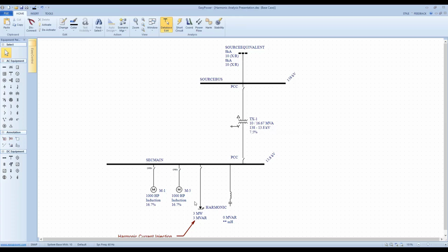If you are adding load, the purpose of the program is to take existing measurements at the point of common coupling and then add that additional load into your model with the measurement load modeled here. So you can of course take your harmonic measurements, model that within the network itself, and then the additional load, which might be a VFD drive, say a 1,000 horsepower drive, you can then add that drive, and then it will be the cumulative sum of those two harmonic producing loads that will result in the performance of the network here.